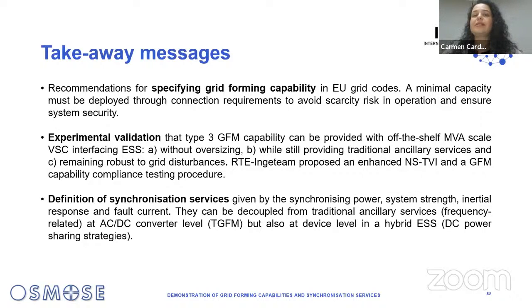It's not exclusive: you can be grid forming and still choose to provide ancillary services, balancing services, or other tracking and flexibility services, getting the same performance without degrading what is expected of a grid forming unit. This definition of synchronization services will help us characterize the required performance from the system, and it's an important achievement for us to succeed in decoupling these services.